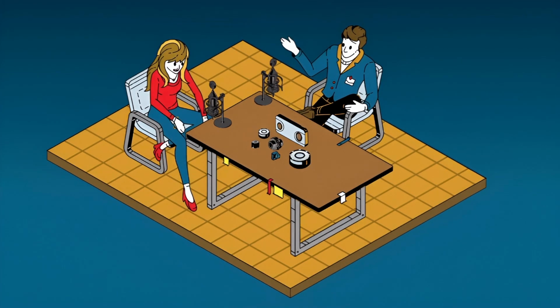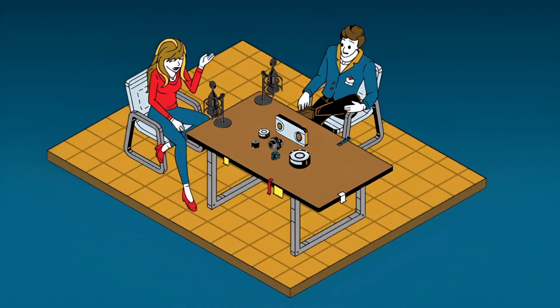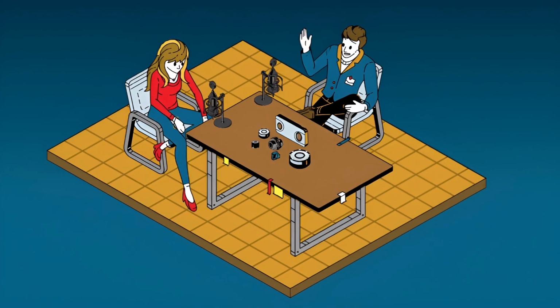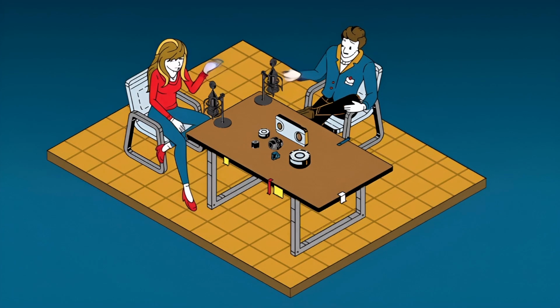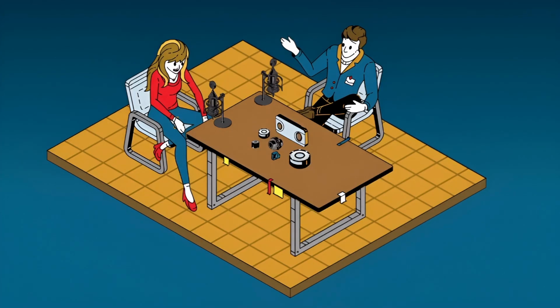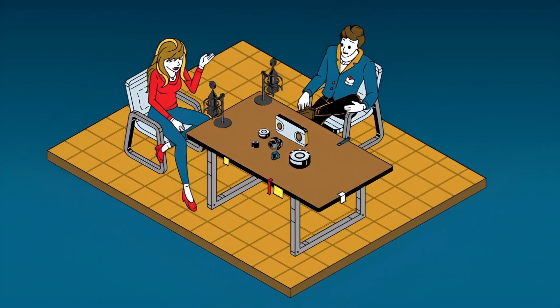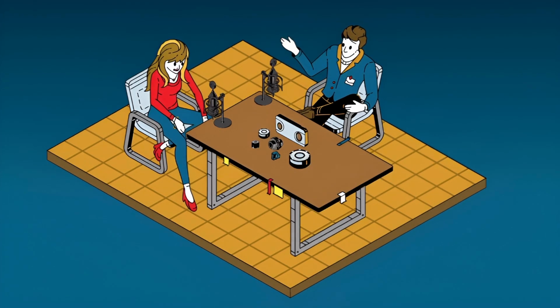So it won't return to zero? Not reliably, no. And once that happens, the data is compromised. If the deformation is bad enough, even a top-tier calibration lab might not be able to fully salvage the cell. So the takeaway isn't just common sense like pick the right capacity, it's understanding that there's a non-repairable window. You have to oversize the capacity for your peak expected load, or use serious overload protection to avoid those microfractures that just ruin the material.